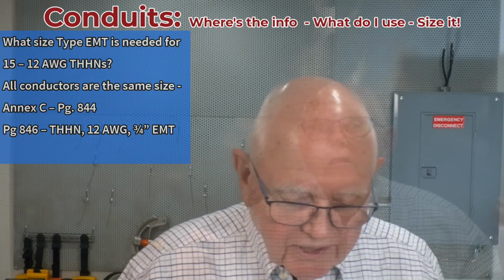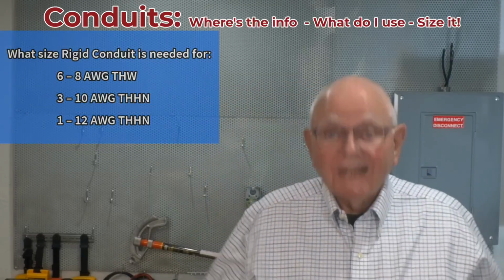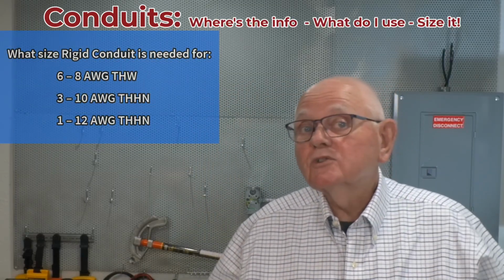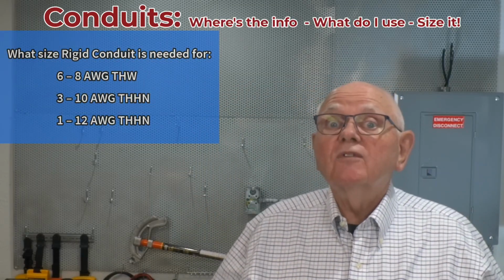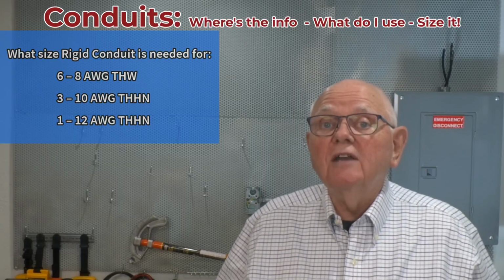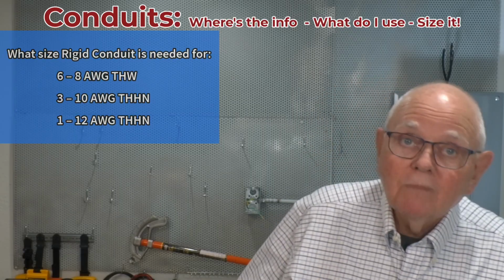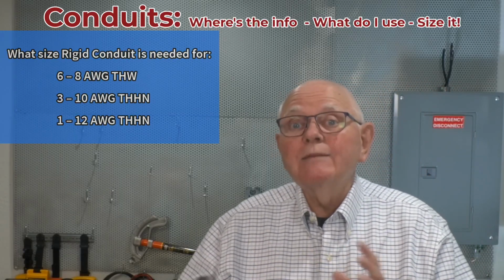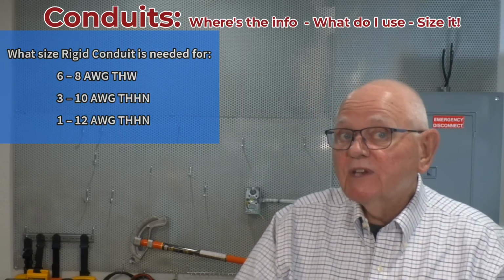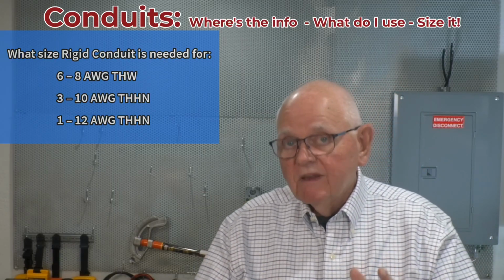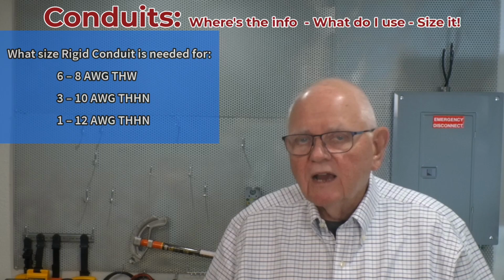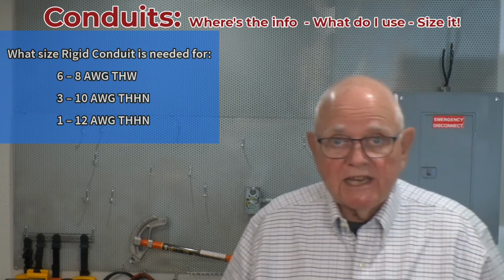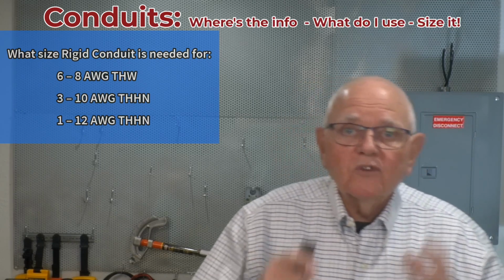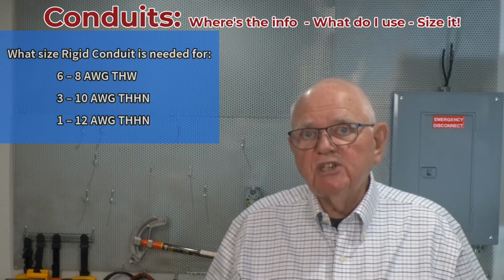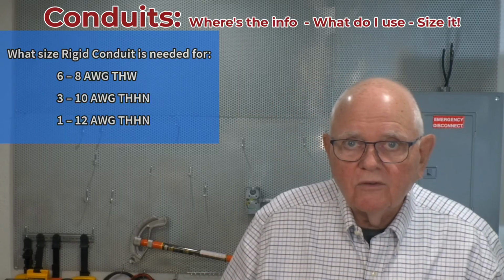size conduit you need. So now let's do an example where my conductors are different sizes. Let's say, for example, I know I've got to use rigid metal conduit, I've determined, and so I'm going to have to first go to table 5 to find out the specifics on all these different conductors. Let's put them up on the screen and take a look. I've got 6 number 8 THWs I'm running. I have 3 number 10 THHNs and 1 number 12.